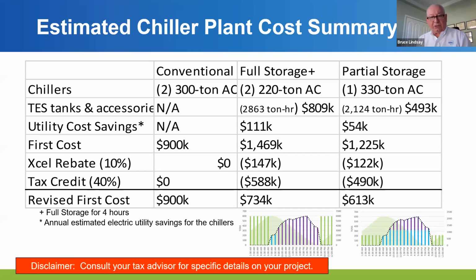I jump to partial storage. I can downsize to 330 tons of air-cooled chillers. I need to put a little bit of tanks in. I save some money, and I have a pretty high premium over the conventional, but I'm saving $54,000 a year - about a 5 to 6 year payback. Not bad. But here's the game changer: if you look at that tax credit at the bottom, I get 40% of that $1.2 million back.